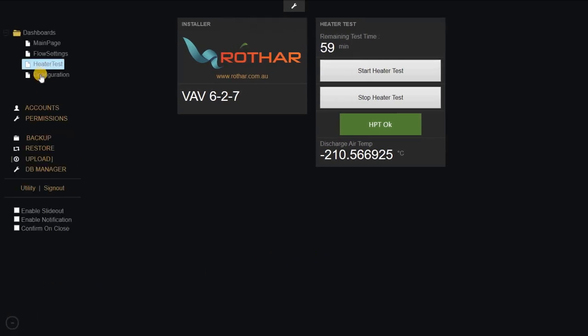It also offers a discharge air temp feedback, so you can see if the heater is actually working without having to put your tongue on it or measure the amperage from the heater bank. This is for electric duct heaters. It would probably work from a heating coil perspective. It would depend on how you wired it and how you programmed it, but this program is specifically for electric duct heaters. We also have a configuration page.